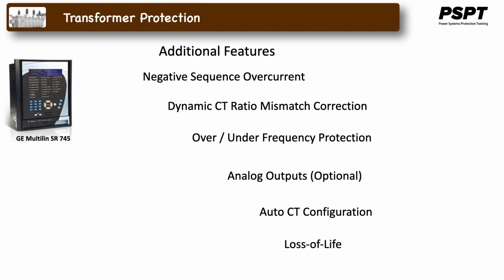The loss of life feature provides an estimate of how much of the transformer's total insulation life has elapsed, based on the IEEE standards guide for loading mineral oil immersed transformers and guide for loading dry type distribution and power transformers.